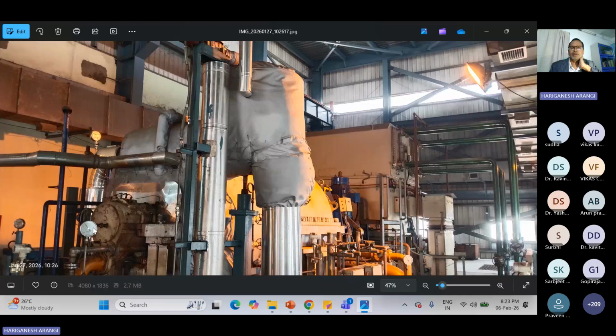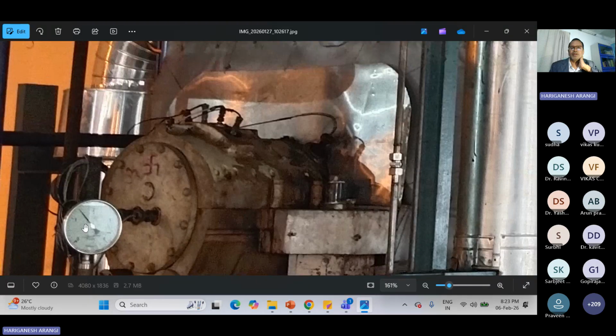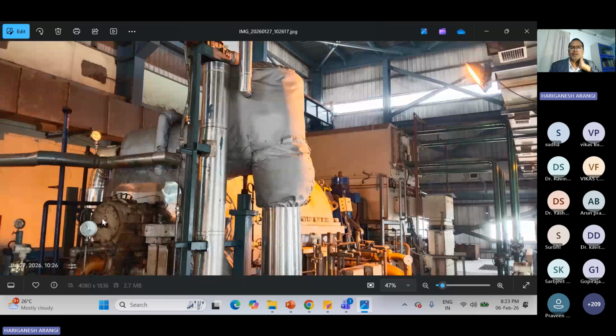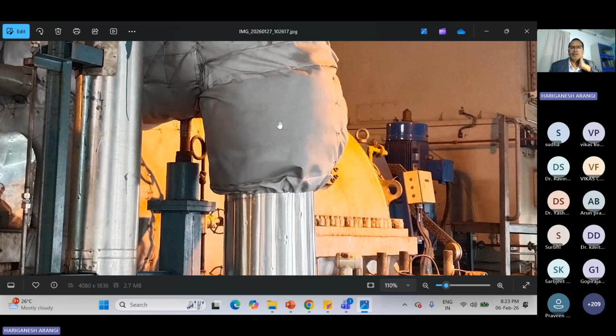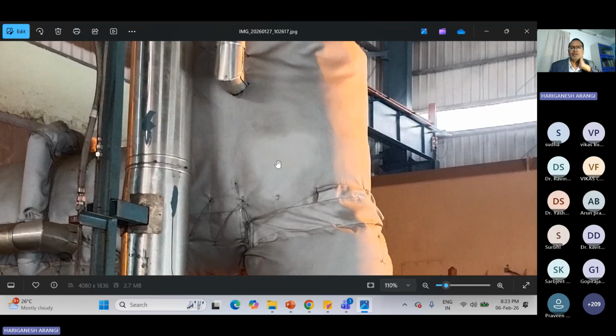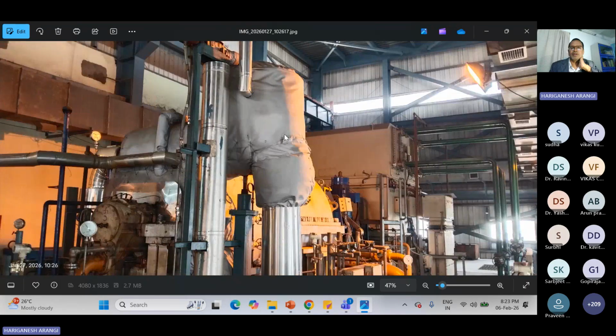From this is the instrument where the temperature and pressure gauge is installed. From this front point up to this is the steam turbine area. Here I will explain to you. From this piping where the insulation is there, the steam piping enters into the first, there will be a chest. The chest means control valves, what we study in our books, the governor.